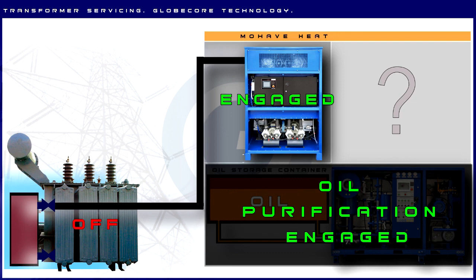The Mojave Heat unit is engaged and the transformer tank is purged with dry hot air. While the tank is filled with dry air and mechanics are busy repairing it, the CMM-4D unit keeps purifying the oil.